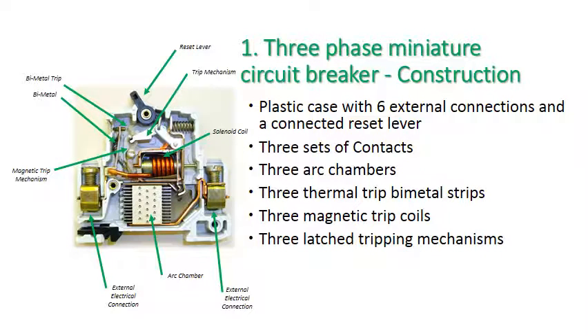So, three-phase miniature circuit breaker construction. This is obviously a single phase circuit breaker. A three-phase miniature circuit breaker has three sets of what you see here, side by side, connected together. As a result, it has a base with six external connections and a reset lever that's joined across all three. There's obviously three sets of contacts, three arc chambers, three thermal bimetal strips, three magnetic trip coils, and last but not least, three latch tripping mechanisms.